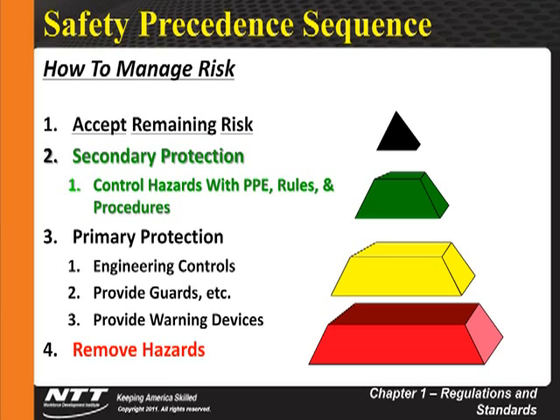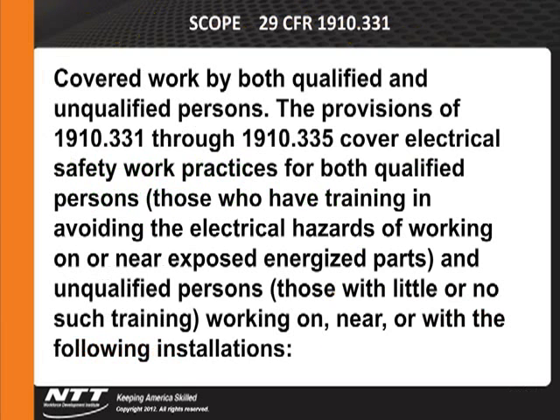But when that doesn't work, then the standard says we've got to go out there and find some way to protect our employees with the appropriate PPE, tools, work practices, and so forth. And once all that's been put in place, the last thing we've got to do is have an employee assume that risk using the appropriate PPE, and find a way that will meet OSHA's requirements for you to demonstrate good faith in protecting that employee. So we look at the OSHA regulation that deals with it.